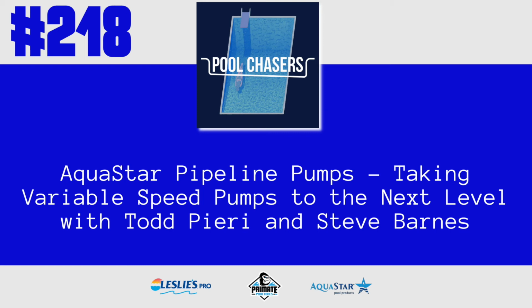So we can have 4 different timings. If we want to run the pool at 1100 RPM for 4 hours, ramp it up to 2400 for a couple hours, and then bring it back down to 1000 for 3 hours at the end of the day, you can do that all on this pump, and it's very easy to program at the pump.